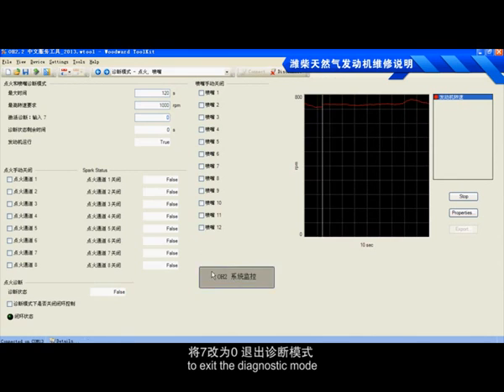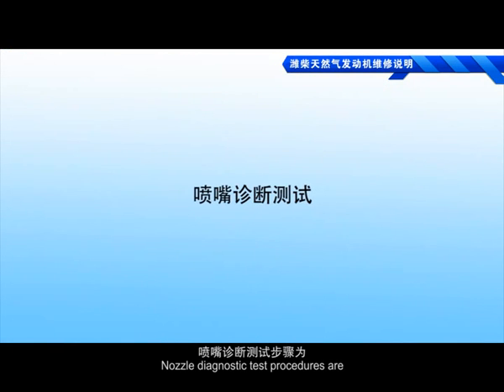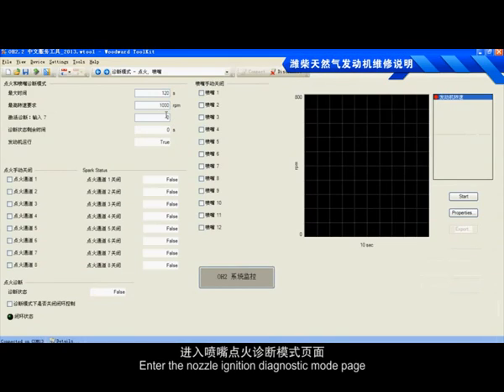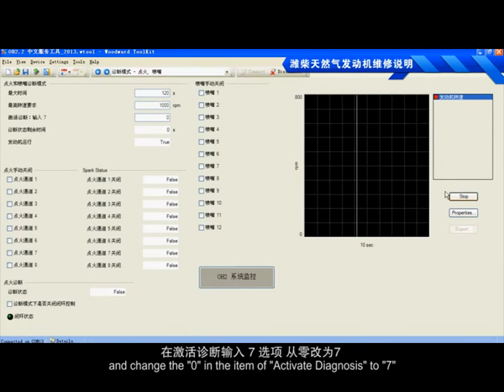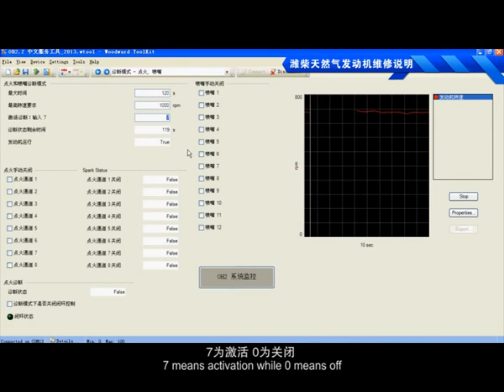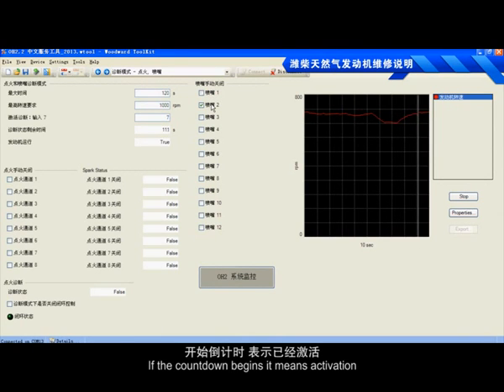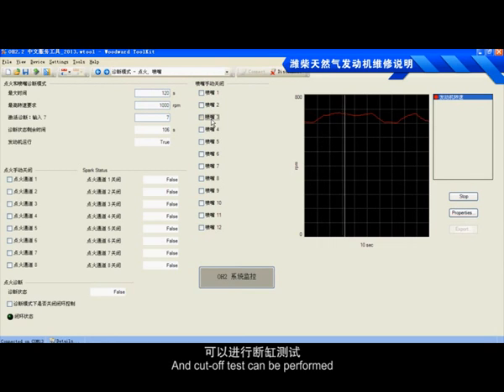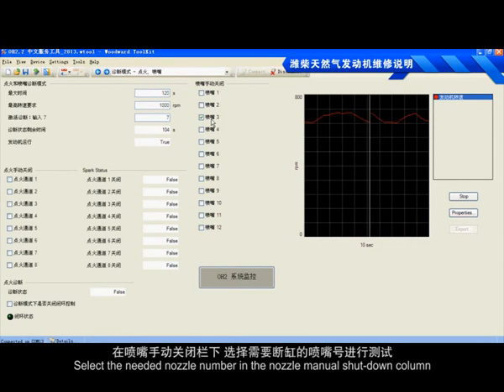To exit the diagnostic mode, the nozzle diagnostic test procedures are: enter the nozzle ignition diagnostic mode page and change the 0 in the item of active diagnosis to 7. 7 means activation while 0 means off. Estimate the remaining time. If the countdown begins, it means activation, and the cutoff test can be performed. Select the needed nozzle number in the nozzle manual shutdown column.